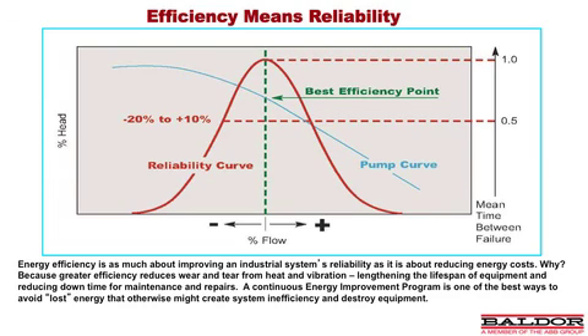This screenshot is showing the Barringer curve. It's named for a gentleman named Paul Barringer, who is one of the foremost authorities on pump reliability. In his diagram here, he's showing you a bell curve. In the center is a vertical line, green dotted line. That is your best efficiency point. And what he's demonstrating here is as you move away, looking at the bottom of the bell curve, away from BEP, your reliability drops off dramatically. The closer you stay to best efficiency point, the greater your reliability.